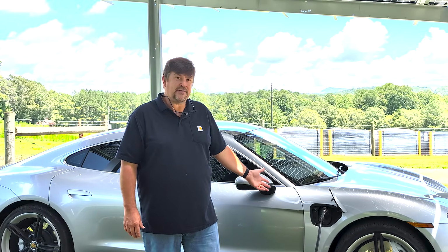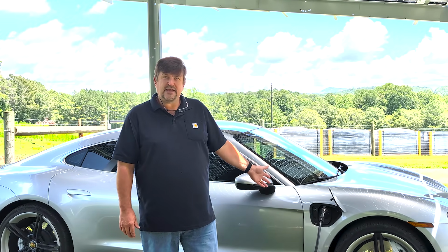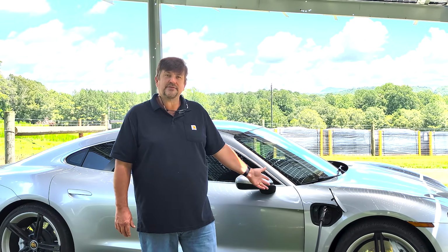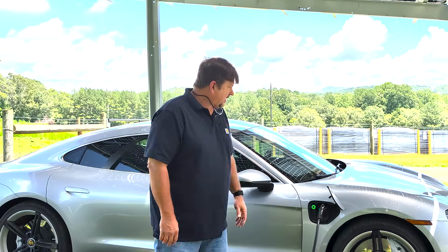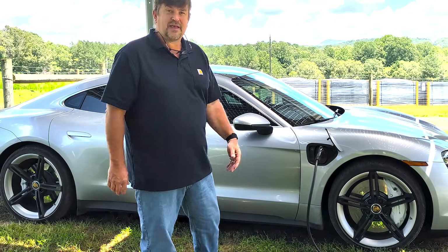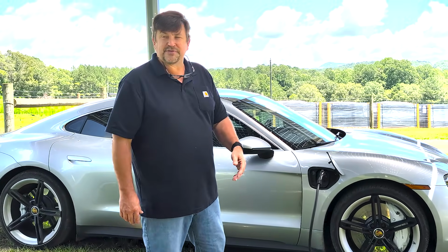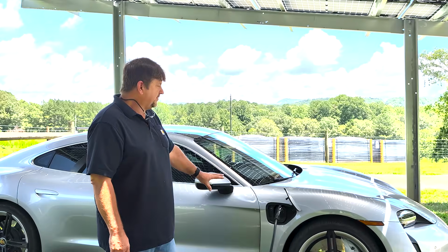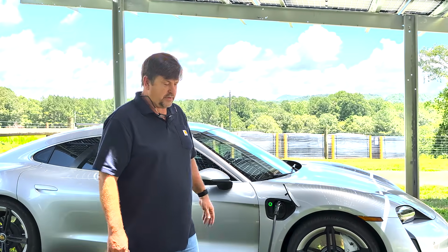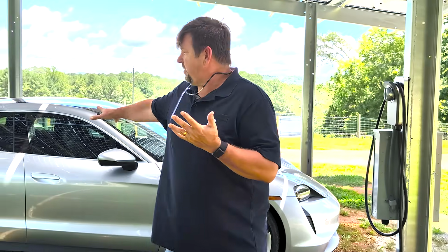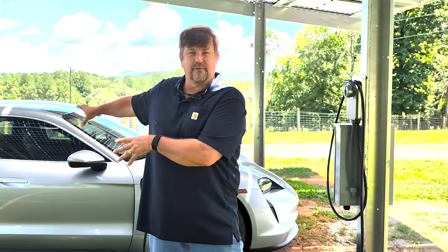We're running an EV, a steady heavy load of about 10 kilowatts, so it's a real test. The car's battery is at 60%, a 93K battery, giving us several hours to run the inverter battery to battery. This could be a constant load for hours, and that's exactly what I'm trying to run - a torture test for a hybrid inverter.